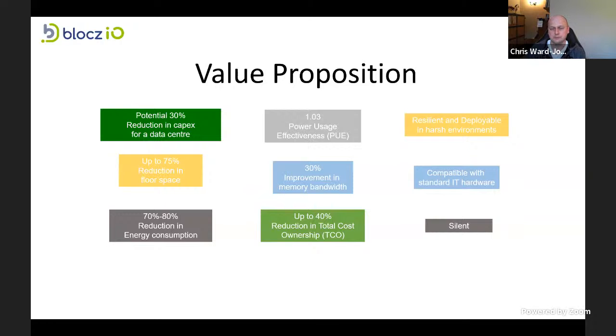And if you built specifically for immersion cooling, not trying to retrofit into an existing space, then your energy reduction is now looking at around about 70 to 80%, which is staggering. And also a 75% or thereabouts reduction in space, because the density is that much greater, which in turn has a knock-on effect with the carbon footprint - to build the building, to produce the cement, etc., and so on.